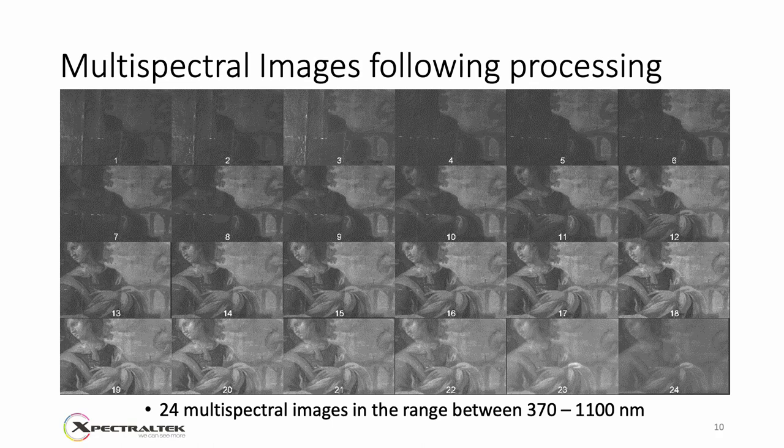When a multispectral dataset is uploaded to the platform, it automatically initiates a series of processing tasks that result in a corrected 3D dataset named Spectral Cube. These processes include image normalization from light inhomogeneities and spectral responses, and image co-registration between the different wavelength bands. The image co-registration algorithm is capable of correcting for 6 degrees of freedom, including translational, rotational, magnification, and image perception angle.